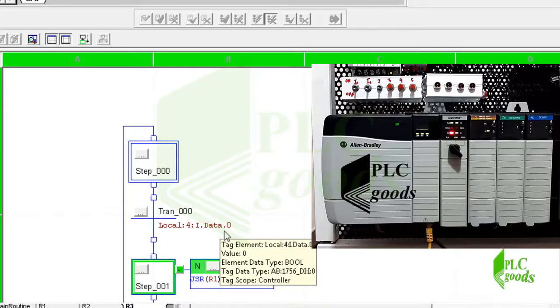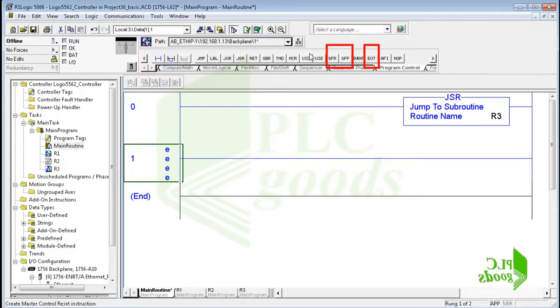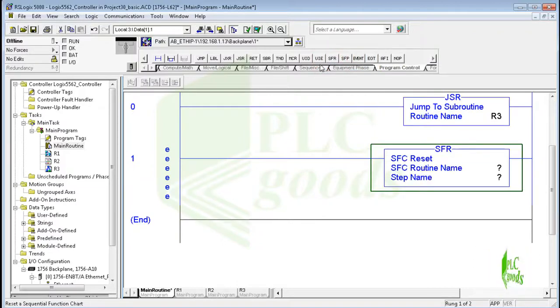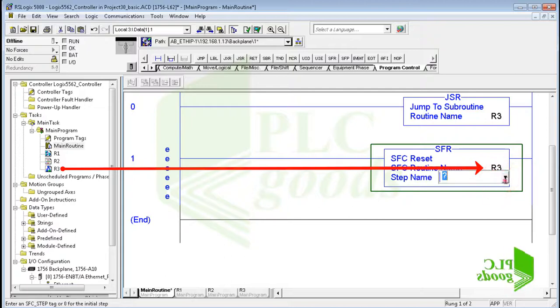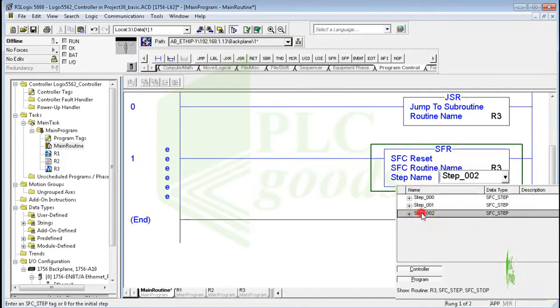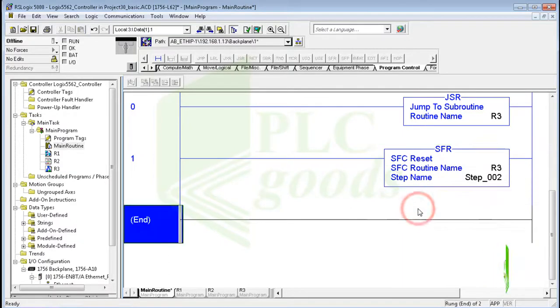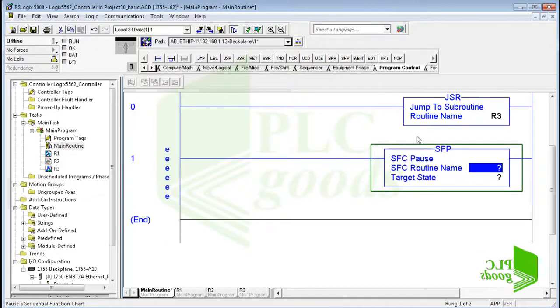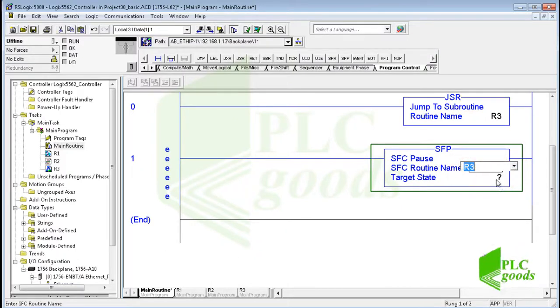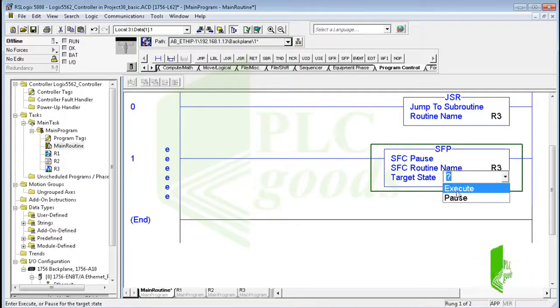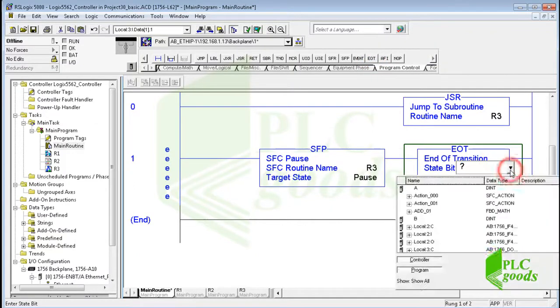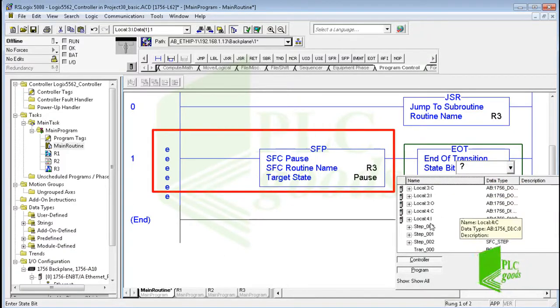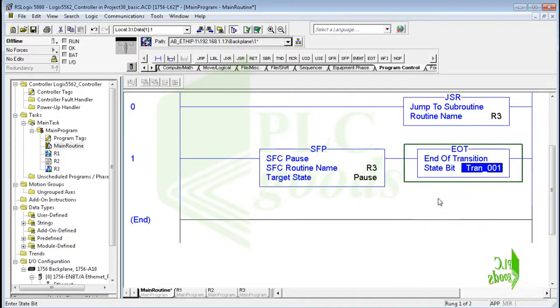I hope you have learned how a sequential process can be programmed using SFC language. Now I can explain three instructions related to SFC programming from the program control instructions. The first instruction is SFR — reset SFC. This instruction resets the execution of an SFC routine at a specified step. The next instruction is pause SFC or SFP; this instruction can pause or restart an SFC routine. The third instruction is EOT — end of transition. This instruction returns a boolean state of its previous run condition to an SFC instruction and can be used to change a transition condition of an SFC routine.